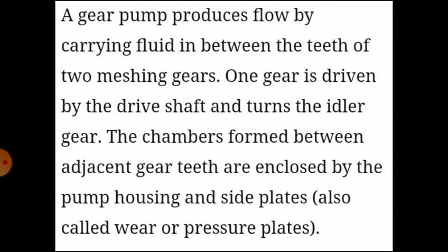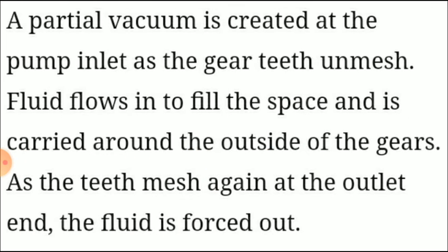A partial vacuum is needed to produce suction in a suction chamber. When the teeth take away liquid along with them from the suction chamber, the reduction in the volume of the suction chamber creates suction. The suction and delivery sides are constantly sealed due to the continuous meshing of the two gears. In the pressure chamber, the teeth deliver the liquid and thus force the liquid into the delivery line. So this is the operation of the external gear pump.